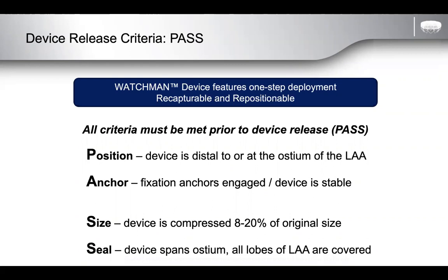The anchorage: are the barbs suitably engaged into the wall of the left atrial appendage? Is the device stable? Is it going to stay in place? Is the size correct? So the fixation depends both on the barbs that are part of the device, as well as the external radial pressure exerted by the nitinol on the left atrial appendage. And so with the old device, we shot for 8 to 20% compression. With the new device, we're shooting for between 10 and 30%, but ideally 20% compression.